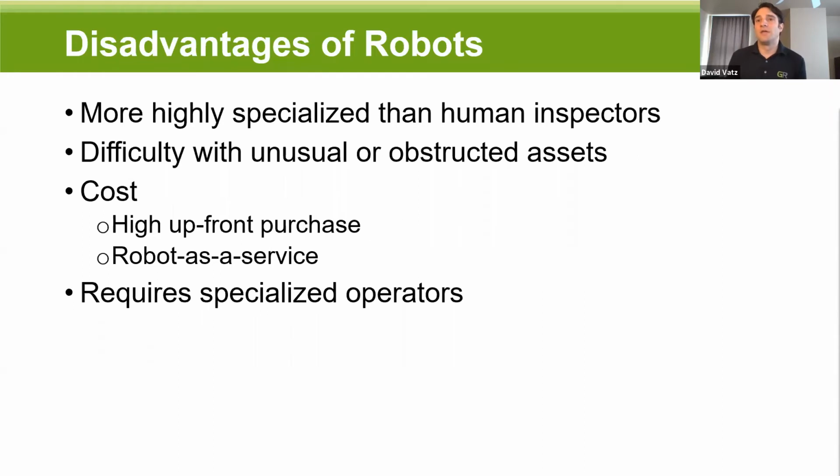Yeah, and again, it really does depend on the specifics of the tank project. However, a lot of times the cost of a robotic inspection can end up being less than just the cost of scaffolding a tank. And we see this in boilers as well. There are some boiler jobs that we do where the cost of scaffolding the entire boiler is more than the entire cost of our inspection. It really depends on the specifics of the job, but a lot of times being able to eliminate that scaffolding will completely pay for the robotic inspection.